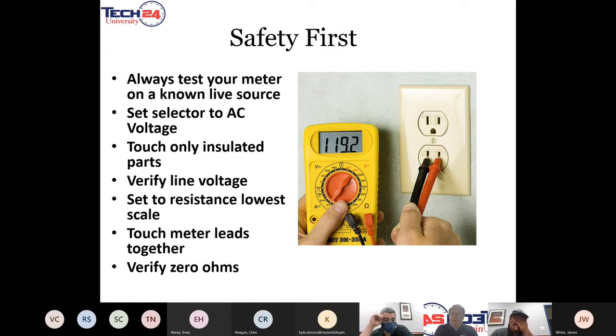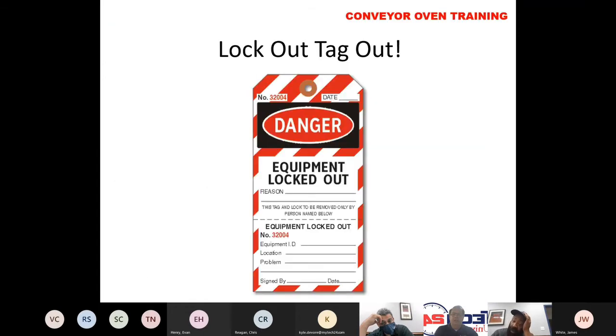If we're going to be safe, we have to know that our meters are operating properly. Please get in the habit of testing your meter when you're out in the field. Check it on a live voltage source so you know that you're reading voltage with it. To make your troubleshooting more efficient, always before you start to ohm something out, touch your leads together. Make sure that your leads will make your meter read 0 ohms. A meter that doesn't read voltage can cause a safety issue and injure a tech.